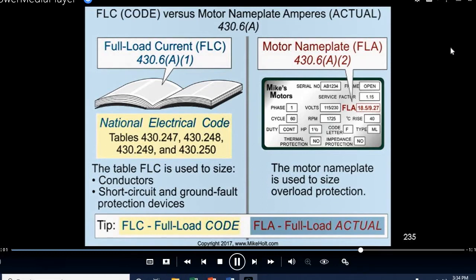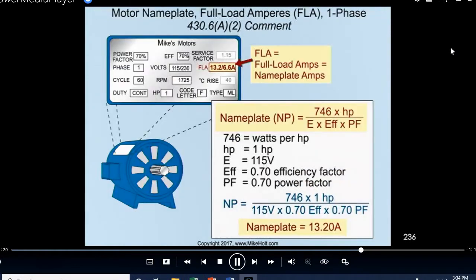For the purposes of this program today, we will never be using the nameplate rating of the motor. We will always be using the motor code requirements because we're going to be using that to size the short circuit and ground fault protection, and we're going to be using that to size conductors. The nameplate is used to size overload, and we're not covering overload in this particular class. We cover that in our calculations class.